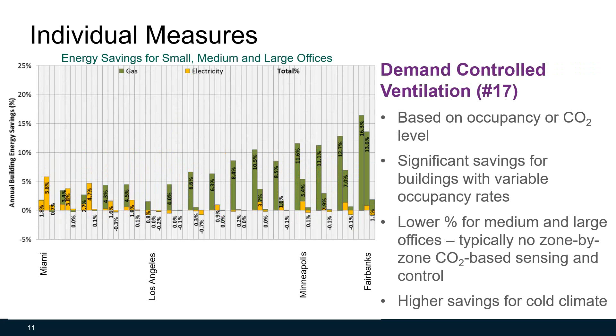Another measure is demand controlled ventilation. It can be based on occupancy sensors, window switches, or CO2 level. When there is no occupant in a space, the temperature of that zone will be reset and the airflow will be controlled at the minimum level. This strategy could have significant savings for buildings with variable occupancy rates. Energy savings will be lower for medium and large offices because there is typically no zone-by-zone CO2-based sensing and control. Higher savings can be achieved in cold climates.